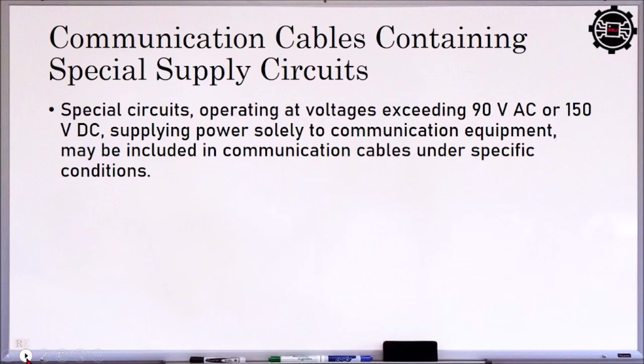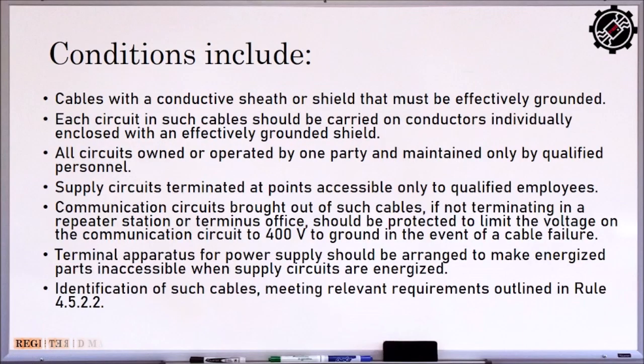Then terminal apparatus for power supply should be arranged to make energized parts inaccessible when supply circuits are energized. So yung mga terminal box, dapat they are locked during energized, kunyari pinadaanan na siya ng kuryente, so they must be locked in order to prevent unnecessary or accidental contact to live parts. Then identification of such cable meeting relevant requirements outlined in Rule 4.5.2, yung identification kanina, that it will also be marked with the company name and also kung anong klase siyang cable at kung para saan siya.